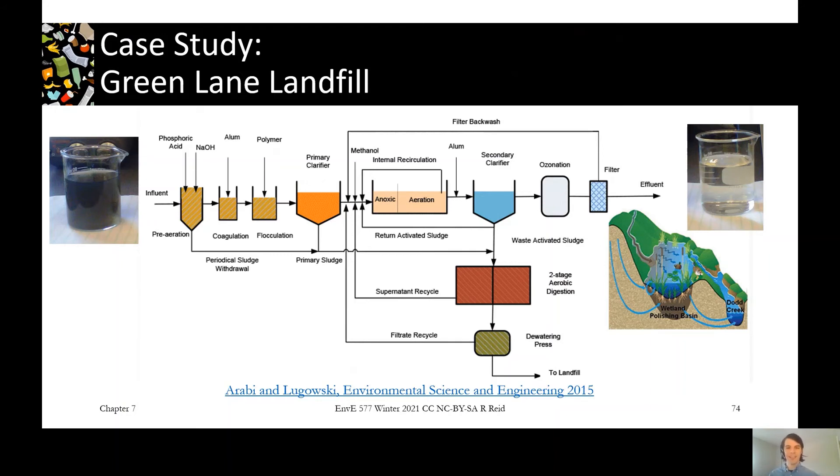Coming out of that activated sludge process, we're doing another coagulation, adding some more alum and another secondary clarifier. Sludge is coming down out of the clarifier and that's going to be aerobically digested, dewatered and put back in the landfill. And then our secondary effluent is going to be ozonated for a disinfection step, filtered and then discharged to a treatment wetland, which acts as a polishing step to treat any additional contaminants before it goes into the final receiving environment.